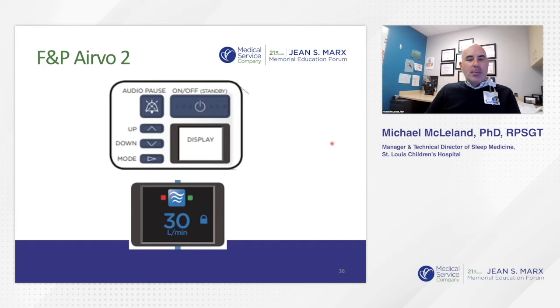So once the machine is set and you choose the setting that you want, we always started out at a minimum of 5 liters per minute for pediatric patients, depending on the nasal cannula, of course. But once we were on this screen, it will stay on the screen. Unfortunately, these machines don't integrate into our sleep systems. So if it was like CPAP or even a ventilator, we can adjust these pressures through our sleep system. With this device, we can't do that. So the staff have to actually go into the room every time they need to increase pressure. But we'll get into when they increase it and how much.